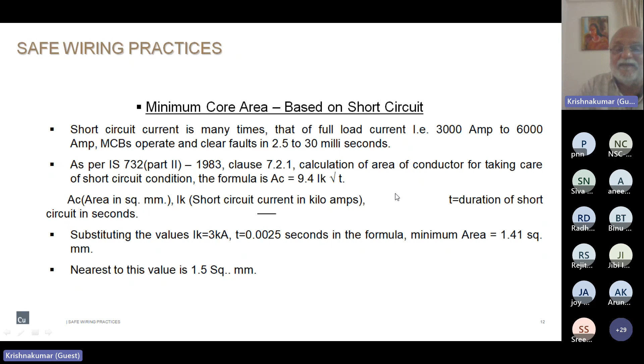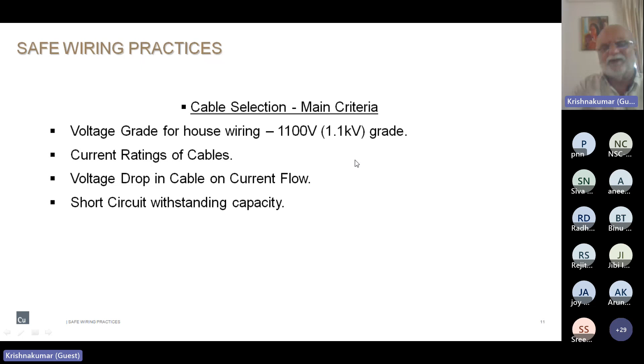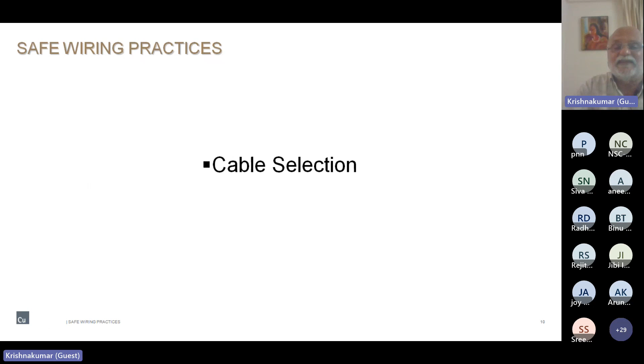You can spread this message that the minimum cross section to be used in house wiring, fixed wiring, is 1.5 square mm wire. That's very important, in spite of the load. These are the two factors to consider: short circuit withstand capacity as well as the voltage drop, or I-squared-R loss, either way you put it.